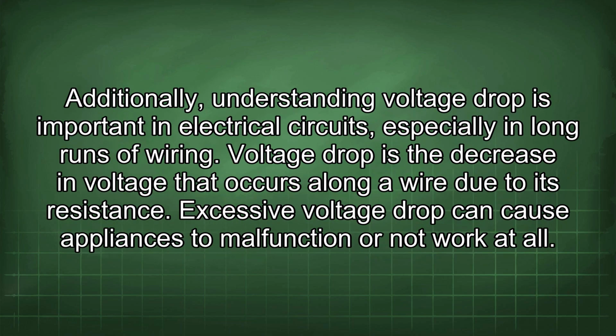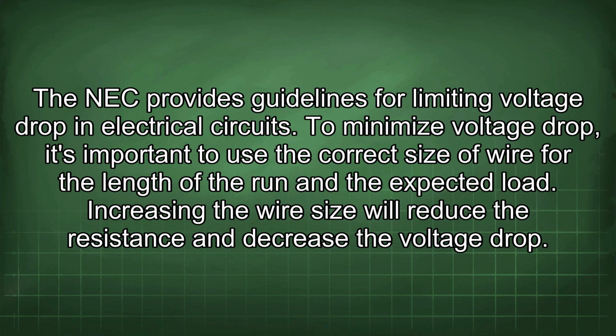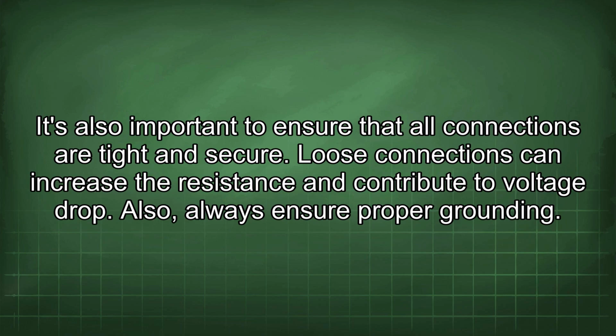Additionally, understanding voltage drop is important in electrical circuits, especially in long runs of wiring. Voltage drop is the decrease in voltage that occurs along a wire due to its resistance. Excessive voltage drop can cause appliances to malfunction or not work at all. The NEC provides guidelines for limiting voltage drop in electrical circuits. To minimize voltage drop, it's important to use the correct size of wire for the length of the run and the expected load. Increasing the wire size will reduce the resistance and decrease the voltage drop. It's also important to ensure that all connections are tight and secure. Loose connections can increase the resistance and contribute to voltage drop.